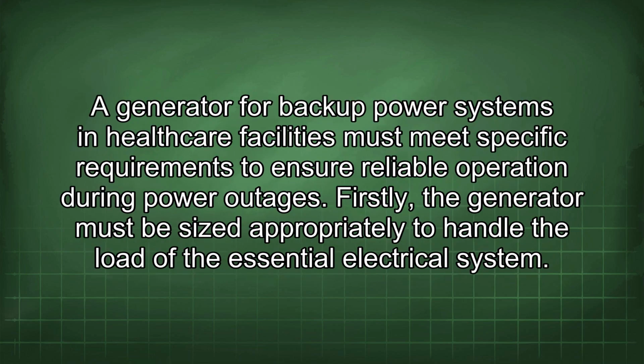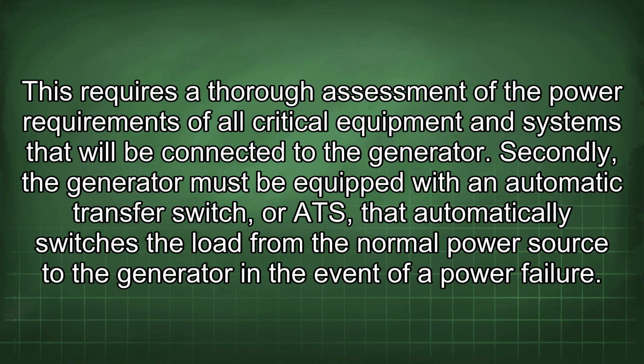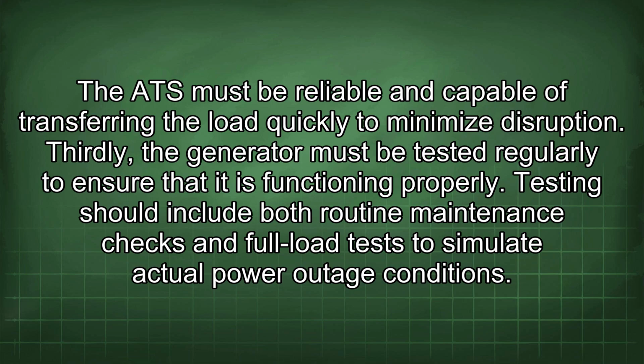A generator for backup power systems in healthcare facilities must meet specific requirements to ensure reliable operation during power outages. Firstly, the generator must be sized appropriately to handle the load of the essential electrical system, requiring a thorough assessment of the power requirements of all critical equipment and systems connected to it. Secondly, the generator must be equipped with an automatic transfer switch, or ATS, that automatically switches the load from the normal power source to the generator in the event of a power failure. The ATS must be reliable and capable of transferring the load quickly to minimize disruption.